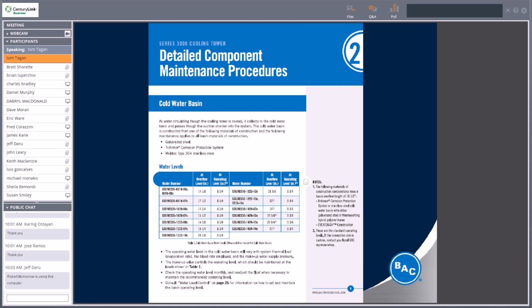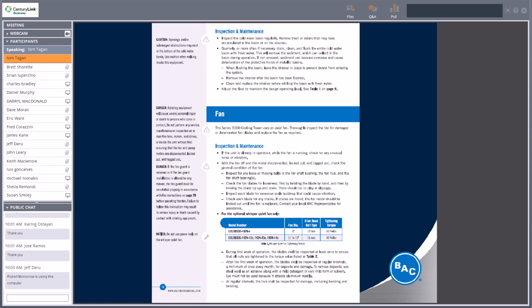One trick that we've learned over the years: if you see ice build up on your cooling tower and the ice is starting from the top down, you've got balancing or flow issues, and your hot water distribution basins are probably overflowing. That's where these water levels come in. If you're building ice from the bottom up, it may be more of a control issue where you're trying to create too cold of a water during a free cooling, low water temperature situation. So a couple of things to think about.